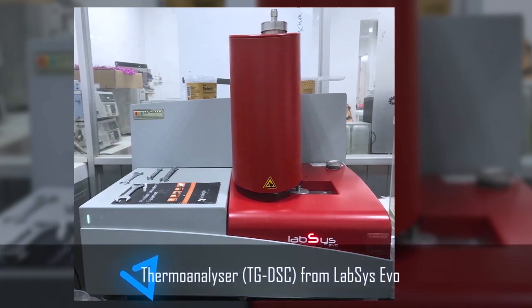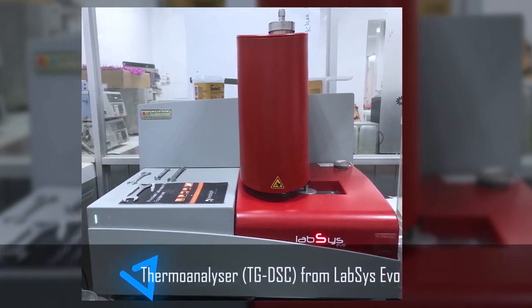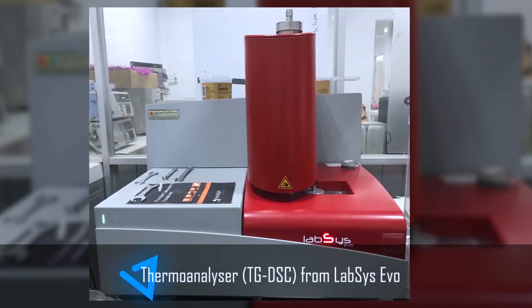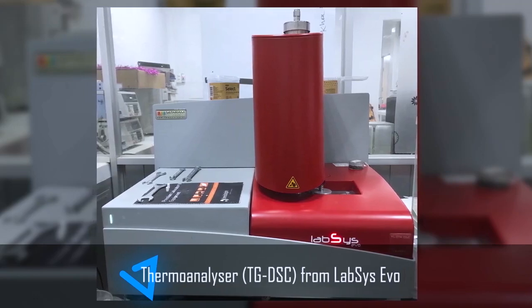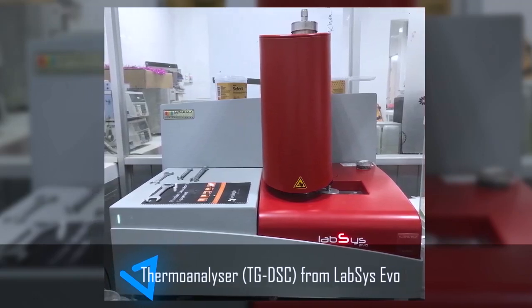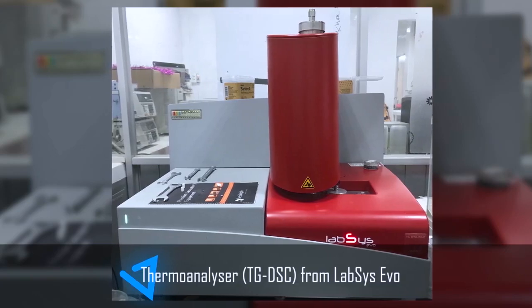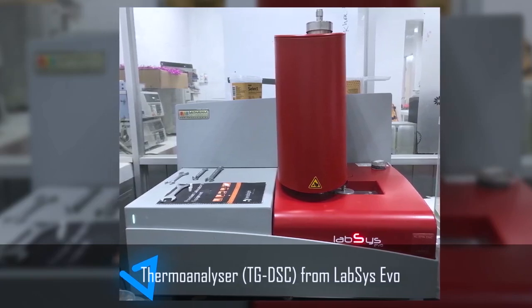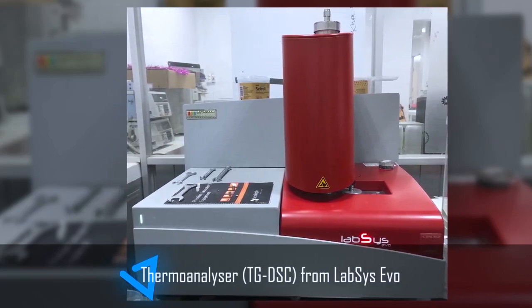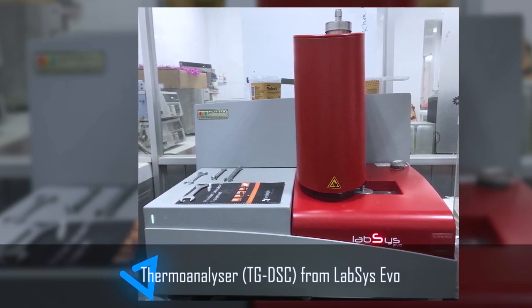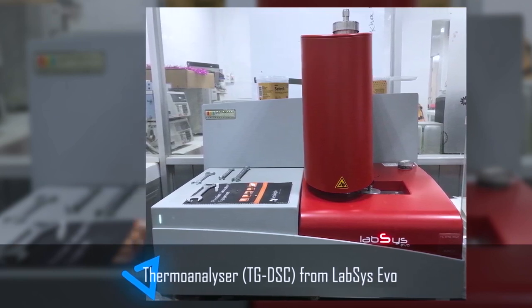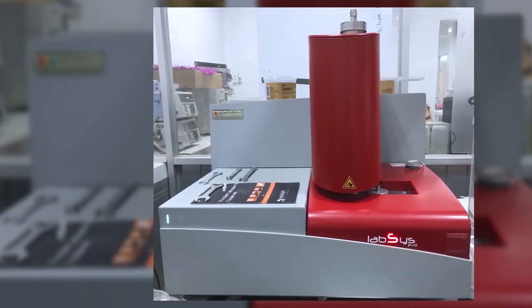Thermal Analyzer TG-DSC is a specialized instrument used for basic scientific research and material science. It is utilized for determining changes in phase properties of samples. Especially, it allows determining essential parameters such as thermal stability and heat flow of materials.